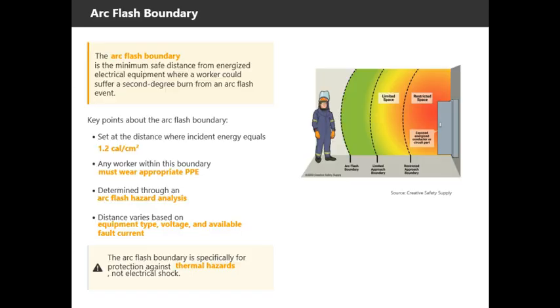Now let's discuss the arc flash boundary, which is a critical concept for establishing safe work practices around electrical equipment. The arc flash boundary is defined as the minimum safe distance from energized electrical equipment where a worker could suffer a second-degree burn from an arc flash event. Specifically, it's set at the distance where the incident energy equals 1.2 calories per square centimeter.